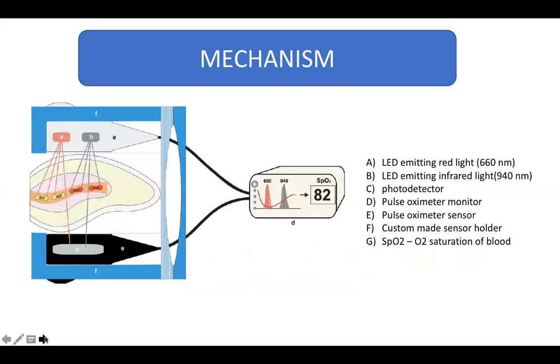The pulse oximeter contains two LEDs: one emits red light at 660 nanometers, and the other emits infrared light at 940 nanometers. Both lights pass through the tooth and are received by a sensor placed on the opposite side of the tooth. Infrared and red light are absorbed in different quantities by oxygenated and deoxygenated blood, and this information received by the sensor is transmitted to a microprocessor, which converts the measurements into oxygen saturation of blood.